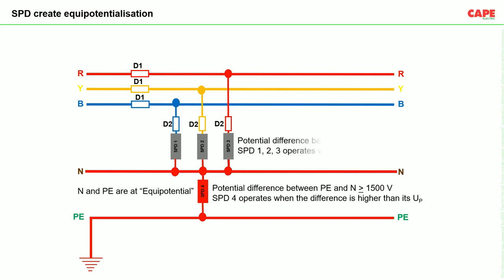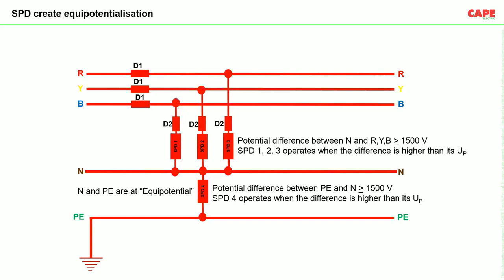But still there is a potential difference between neutral and B, neutral and Y, and neutral and R. Because of this potential difference, SPD 1, 2, and 3 operate simultaneously. And because of this operation, the voltage which was at neutral is again reaching R, Y, and B. Now you see our complete system is at equipotential. R, Y, B, neutral are at the same potential. So there won't be any potential difference across the load and our load is not going to fail.